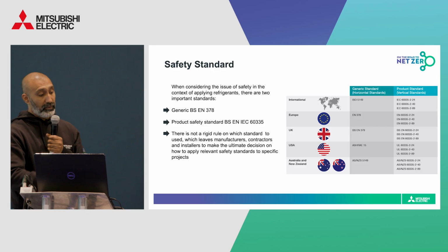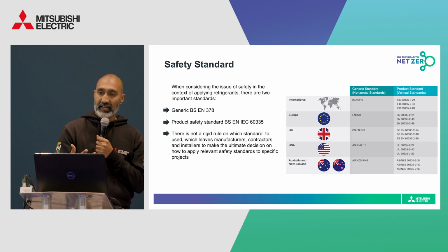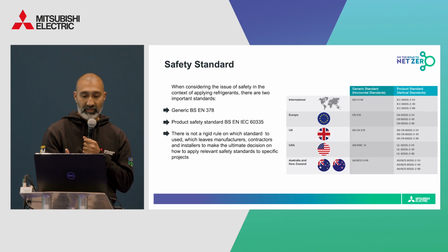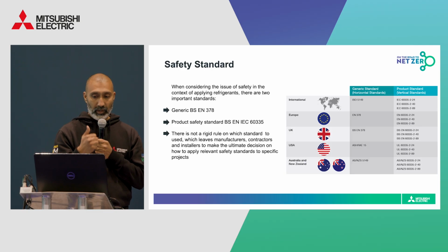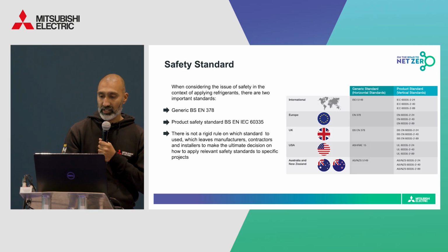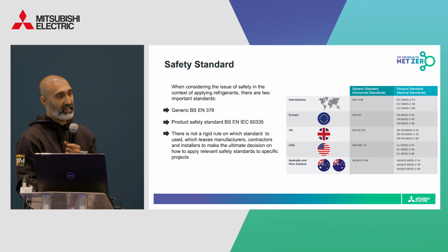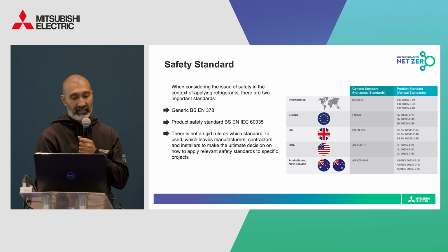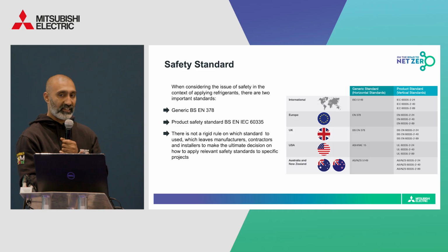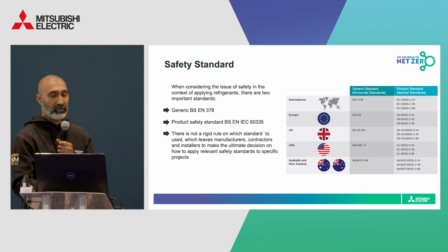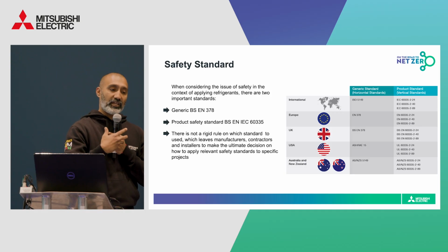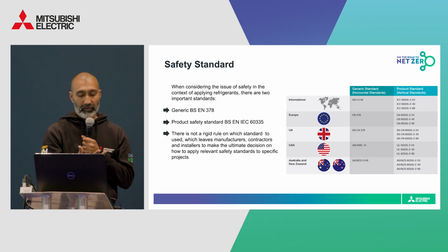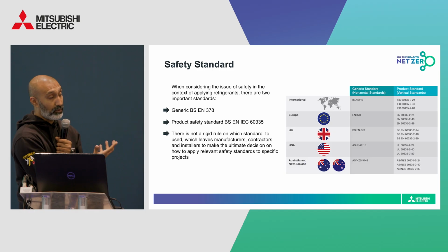Okay. When we look at the future of air conditioning, really the same factors that have driven its evolution over time will continue to shape its development: low carbon buildings, the growth of hydronic solutions, low GWP refrigerants, and the advancement in control and monitoring solutions. But adopting new refrigerants does bring some challenges. Most of the new low GWP refrigerants tend to have a classification as either mildly flammable or flammable, which makes installation and design something that you need to be a little bit more considerate and careful around. Which then brings us nicely to the importance of standards.